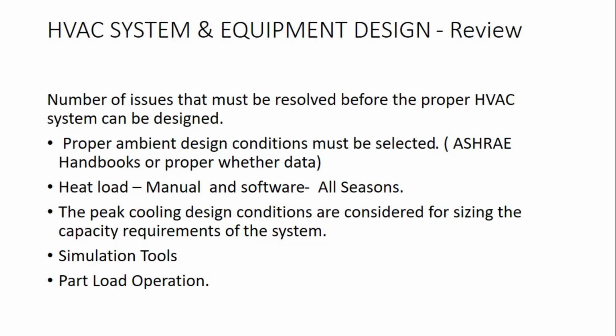You must also keep in mind that peak load occurs only once a day, maybe for a few hours, but we select equipment based on a factor of safety. As an HVAC design engineer, you want to select the optimum design plant, but you also have to use creativity in selecting equipment. The basic fundamental of HVAC system design starts with data collection, followed by heat load or cooling load estimation.